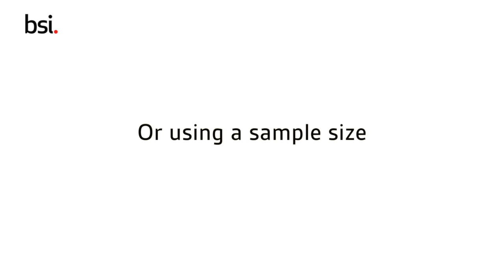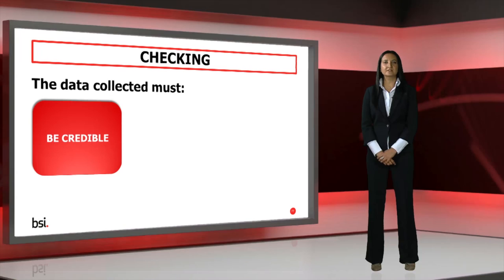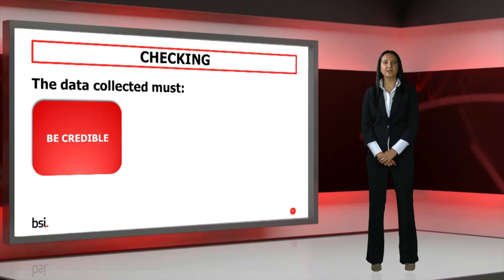The development of this metering plan will have been part of your action planning. It is important that the data you collect is credible. When developing your energy baseline, make sure that you do not fill in any missing data, as this will form the benchmark for your future activities. If in doubt, wait for a longer period to obtain suitable data.